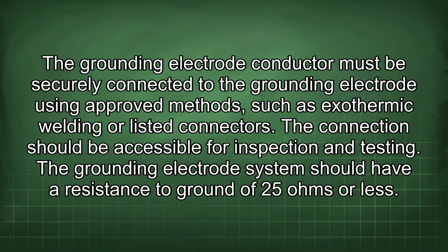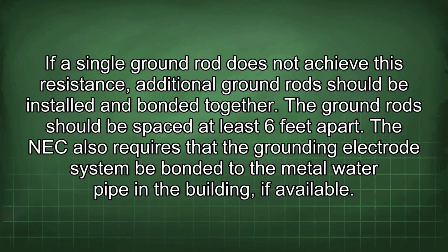The grounding electrode conductor must be securely connected to the grounding electrode using approved methods such as exothermic welding or listed connectors. The connection should be accessible for inspection and testing. The grounding electrode system should have a resistance to ground of 25 ohms or less. If a single ground rod does not achieve this resistance, additional ground rods should be installed and bonded together. The ground rods should be spaced at least 6 feet apart.